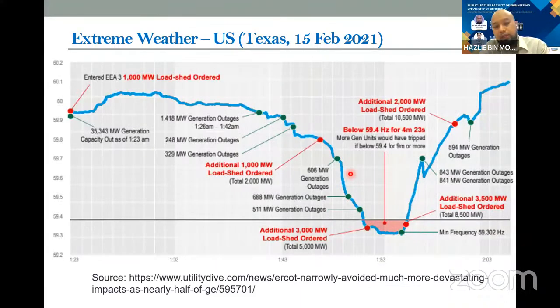Okay, so if you look at the frequency response again, when there is a difference between total generation and total load, total demand, the frequency will change. So here we see that this is normal. This is the start of the 1000 megawatt load shed order. I mean, they need to remove some of the load in order to recover.